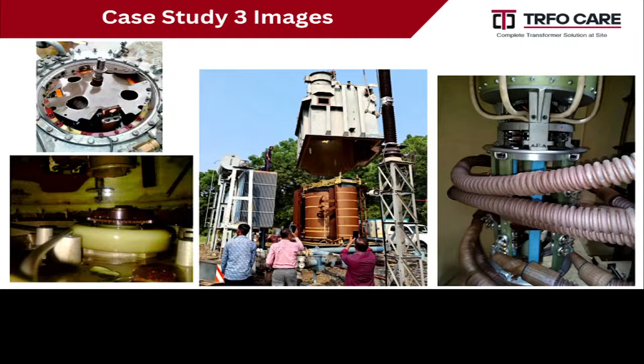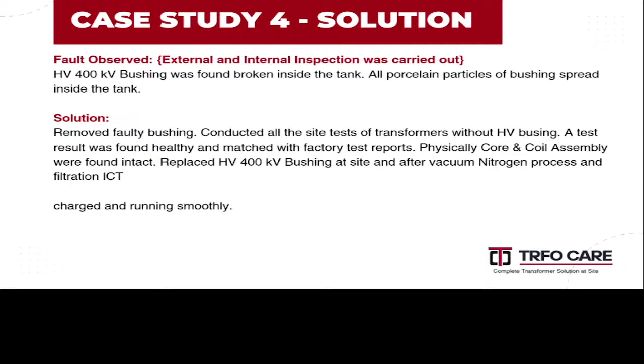This is a 167 MVA, 400 kV class transformer near the Raigad region. The complaint was that a bushing flashover was observed. Externally it looked as if the bushing was completely damaged. If we look at the transformer, nobody can say the transformer would have been saved. The bushing was completely blasted. So the customer called for the internal inspection. We went inside and checked everything. Apart from the bushing, nothing had happened to the transformer.